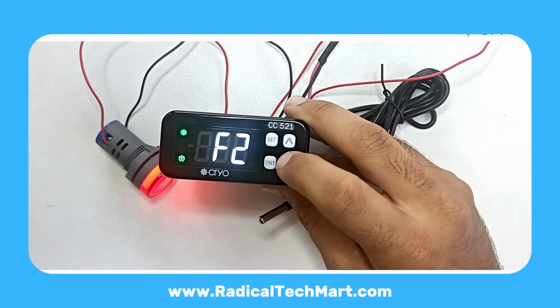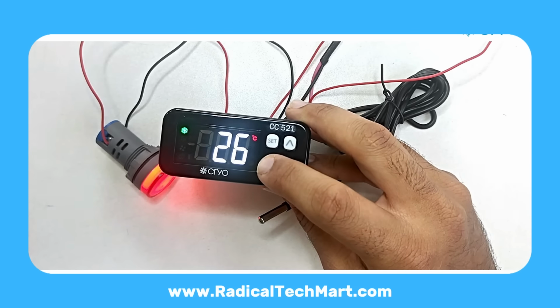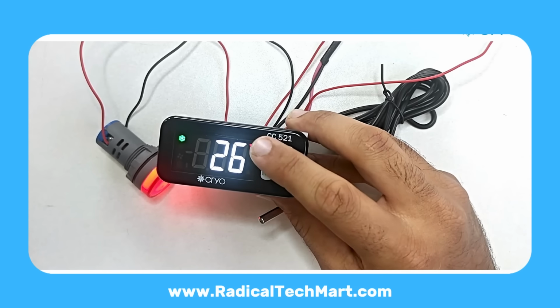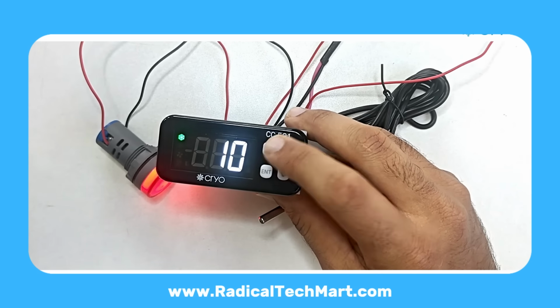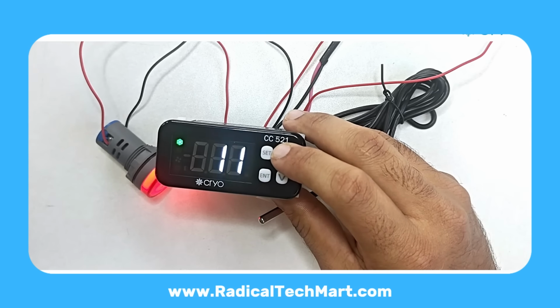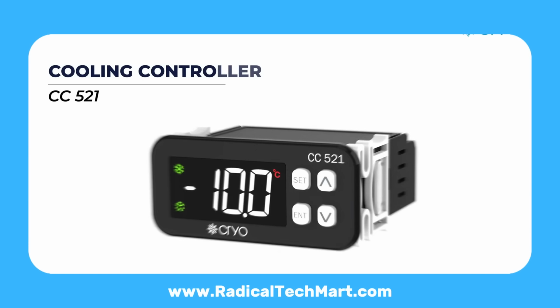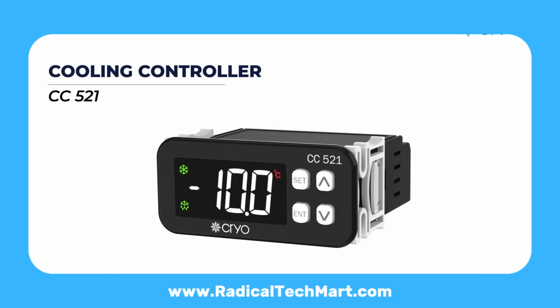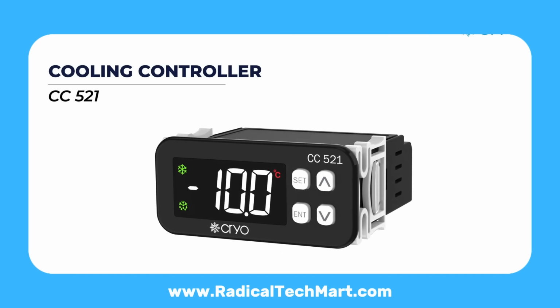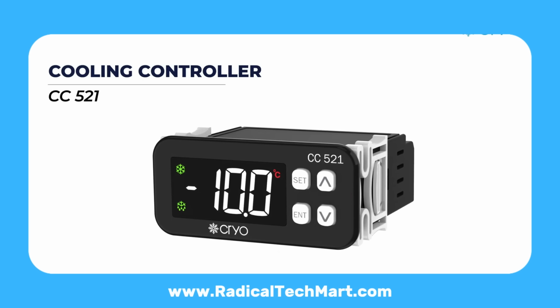After configuration, you can return to normal display mode. Press set once to view or change the current set point. Adjust as needed and press enter to save. And that's the complete guide to the CC-521 temperature controller, covering wiring, delay timing, defrost logic, and parameter settings for air dryer applications.